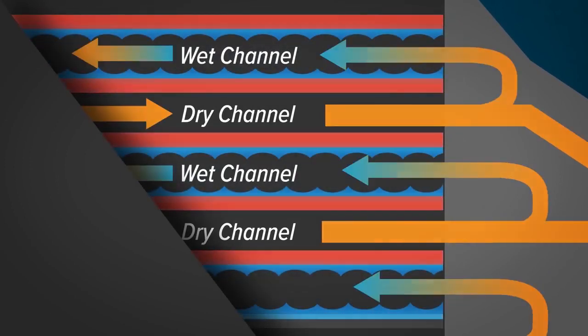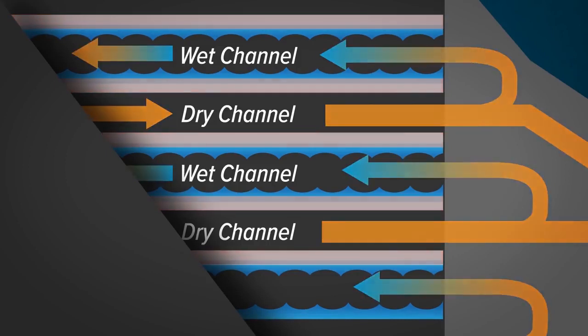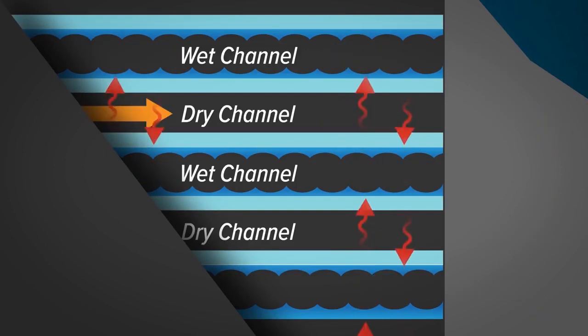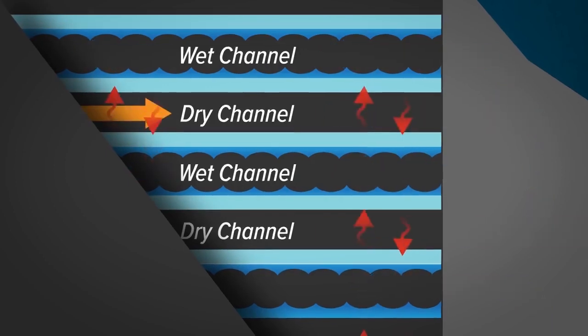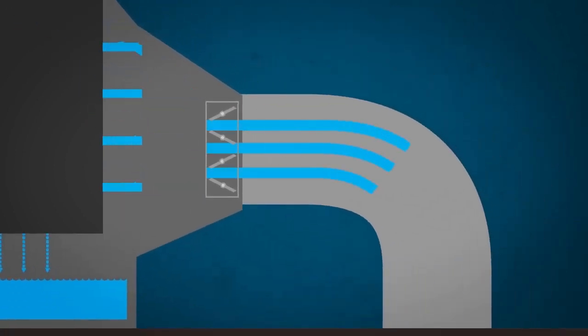The evaporative process cools the wet channel walls. As these walls cool, they absorb heat from the dry channel air, cooling the air delivered to the building. The portion of air supplied to the building is controlled by a damper that is set for the specific application.